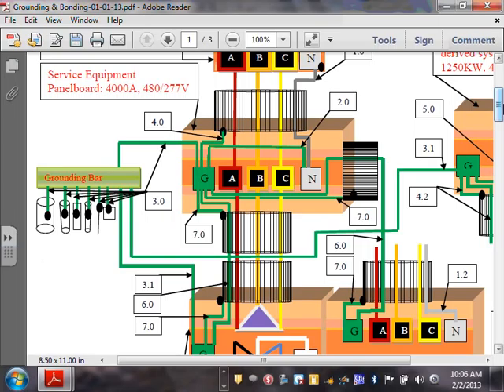The easiest thing, guys, is a grounding fitting here that you put with a grounding jumper, right? And you grab that wire and you tie it to the ground. That's typically the easiest way that you do at the service. You can have a grounding clamp around the conduits, clamp, right? And you tie it. Any comments, guys, about this material?